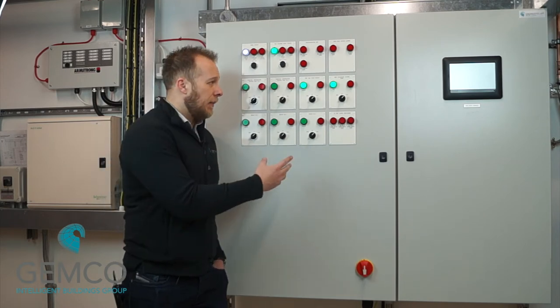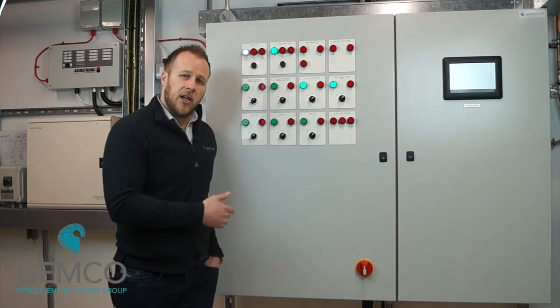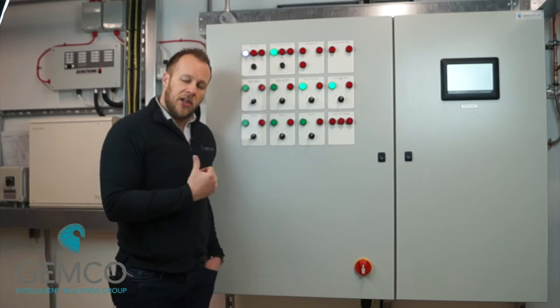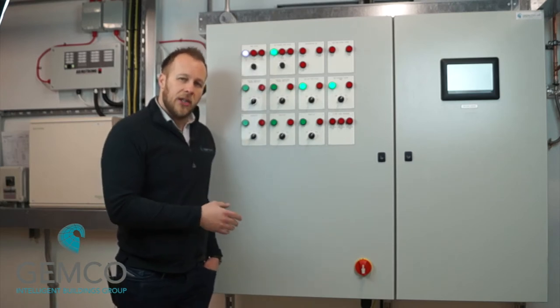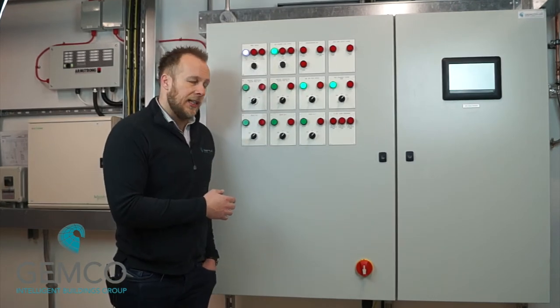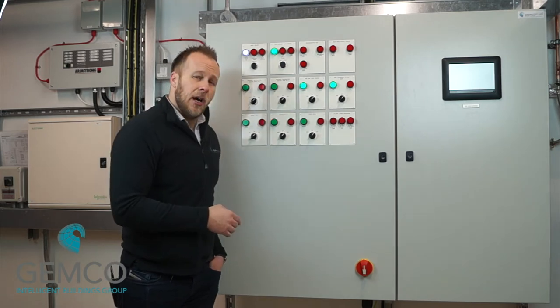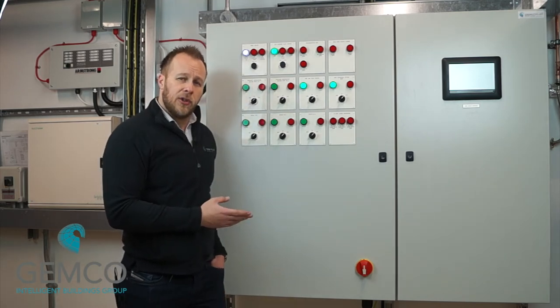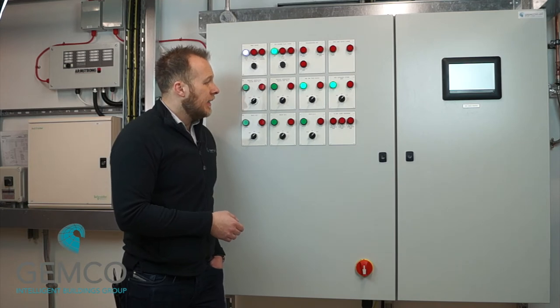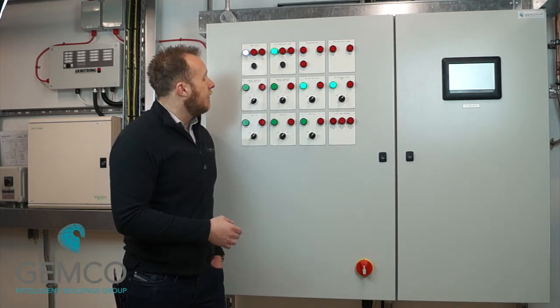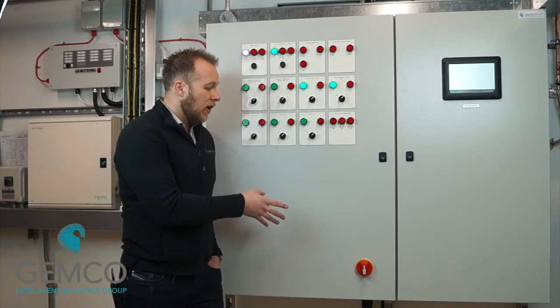So if you ever come in and the plant's running and you think the time zone's off, chances are it's because it's freezing cold outside and you've got a frost activating. And it would let you know on the BMS if a frost condition has been activated. Okay, so that's really everything there is to know about the panel overview.